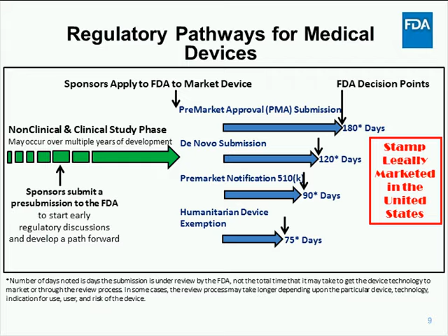So for example, we receive several dozen PMAs each year. These submissions are the highest risk and require clinical data. These are Class 3. A second pathway is the 510K submission pathway. We receive several thousand each year, and they typically do not contain clinical data, but are supported by non-clinical data and bench testing and review of prior submissions that may have contained clinical data. These are typically Class 2.